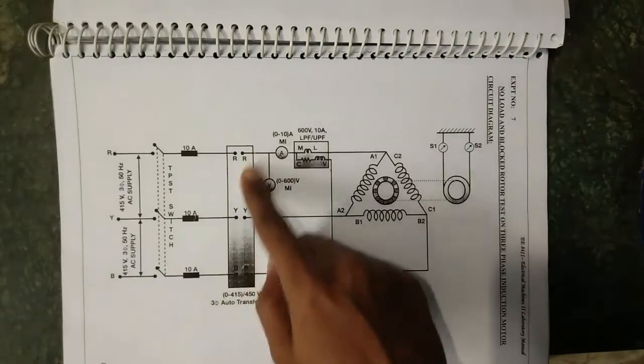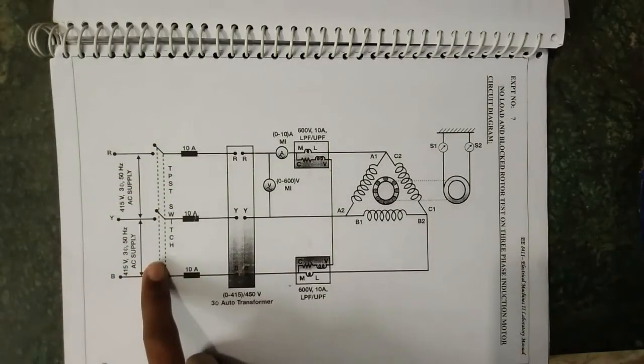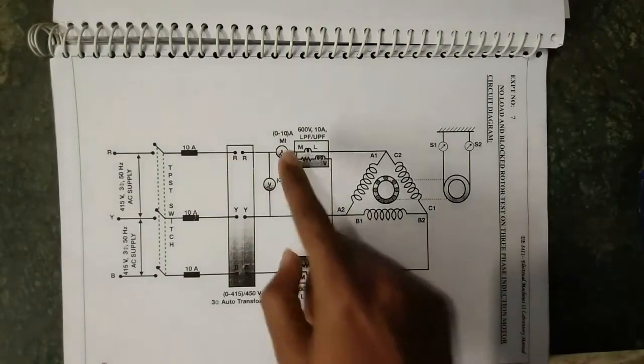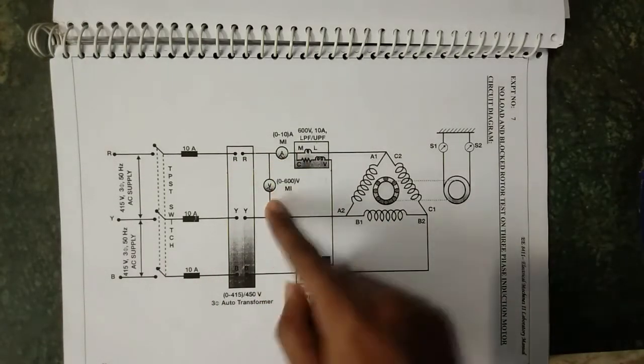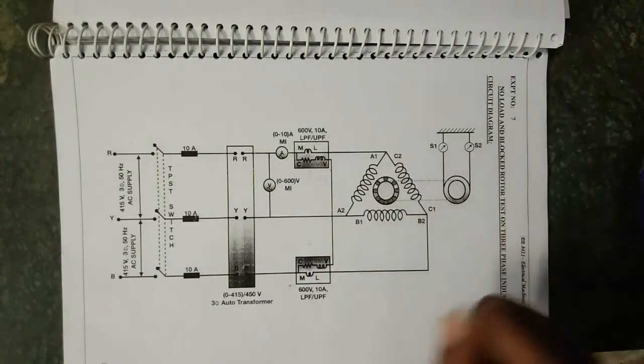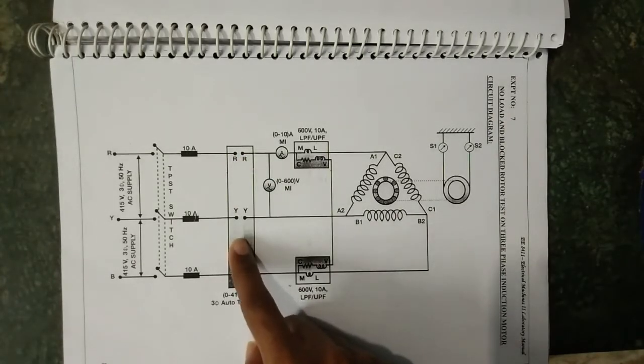The procedure for no-load test: with the auto transformer in the minimum position, the supply is switched on and the voltage is increased to rated voltage. All the meter readings—ammeter, voltmeter, and the two wattmeter readings—are noted down under this no-load condition. The auto transformer is brought back to the minimum position and then the supply is switched off.